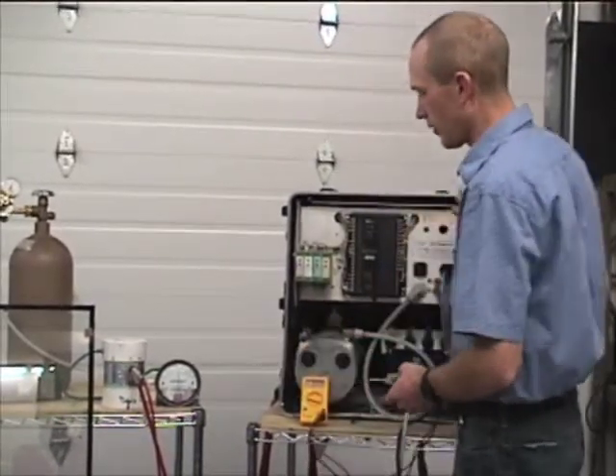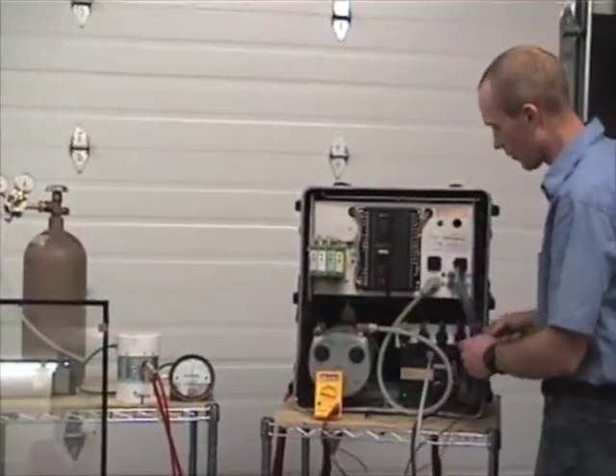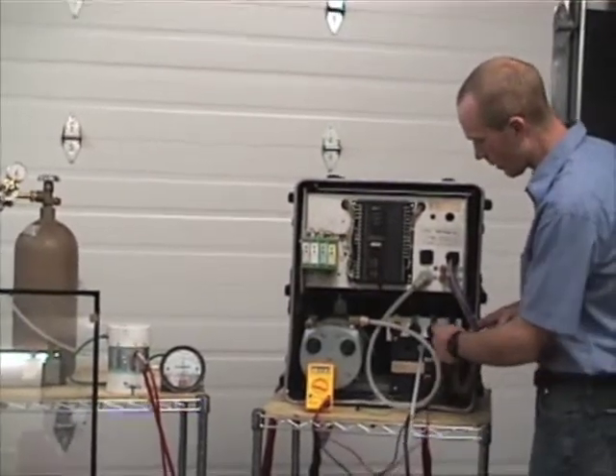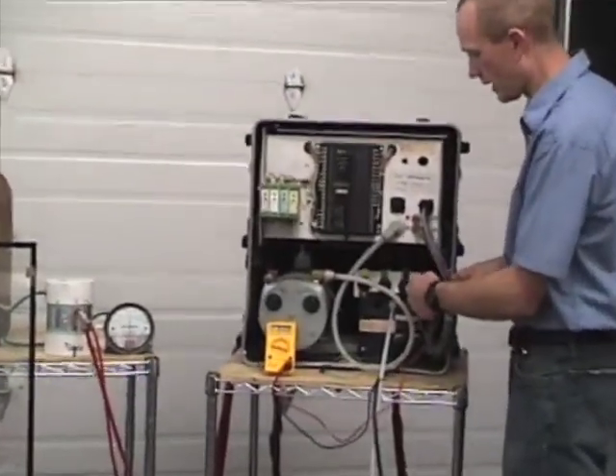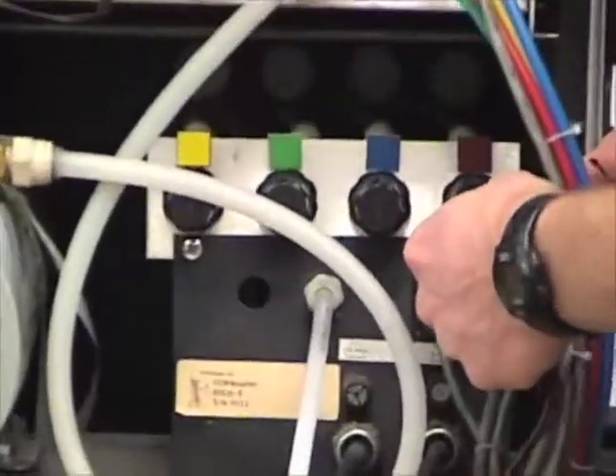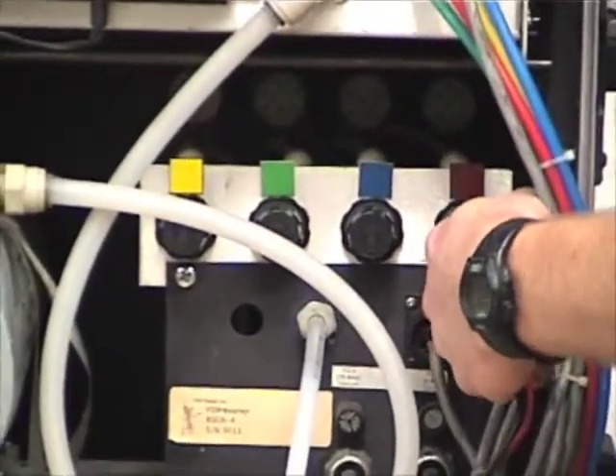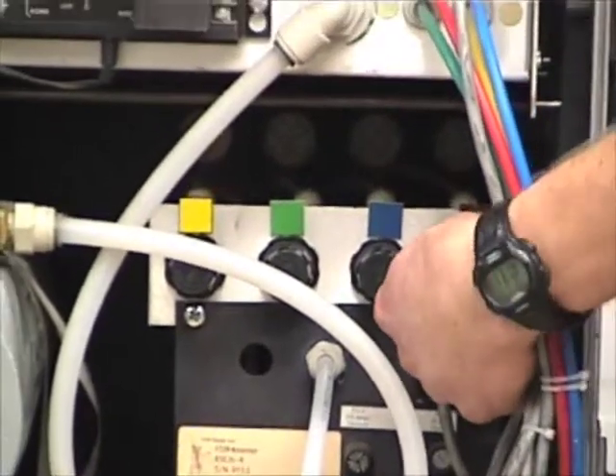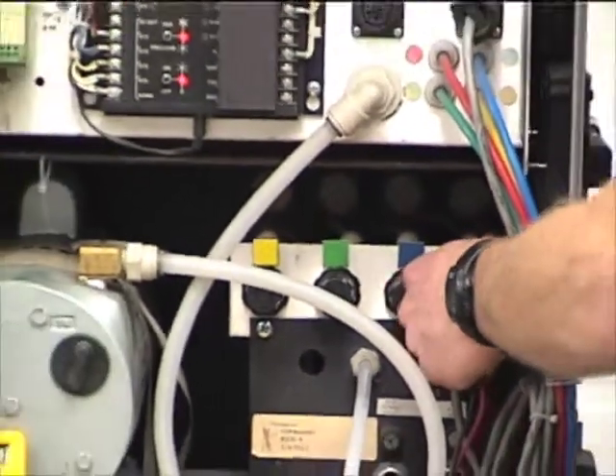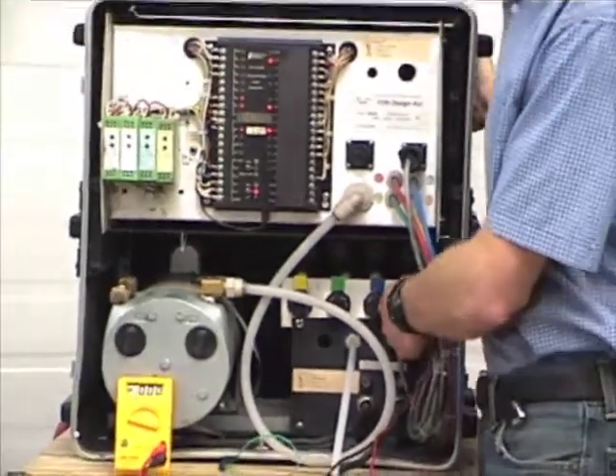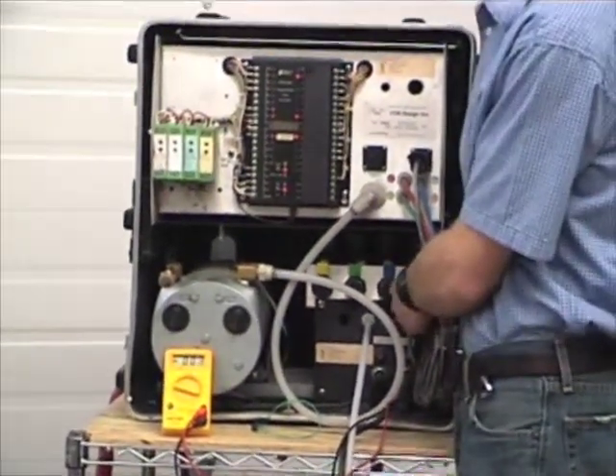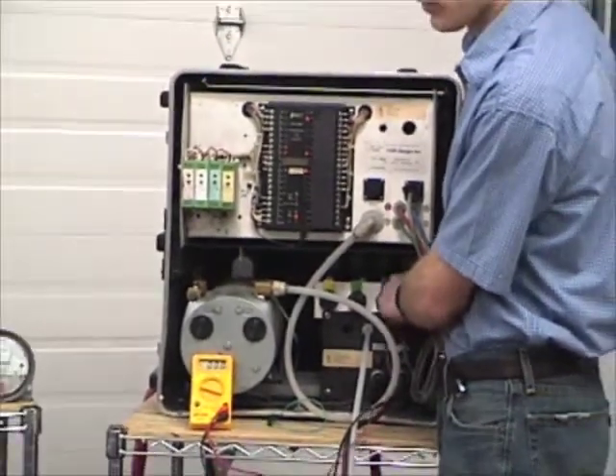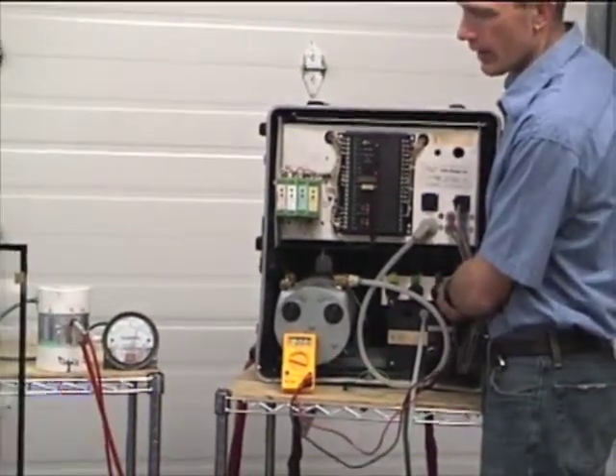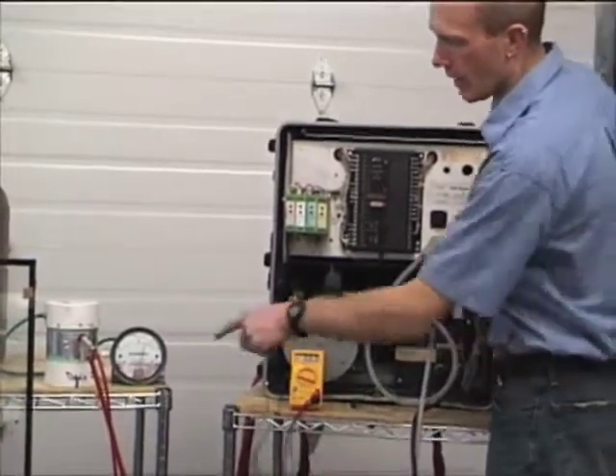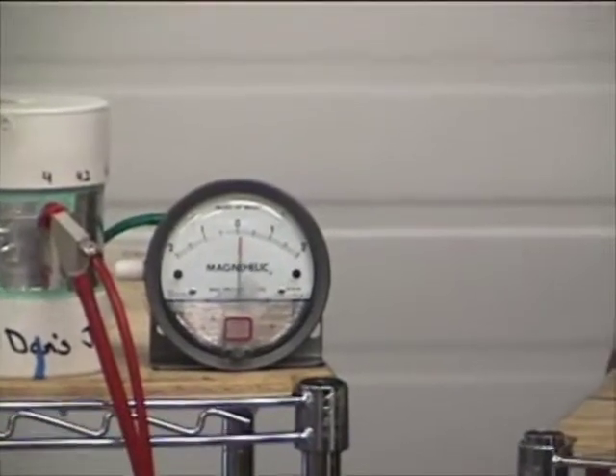I'll go ahead and start the machine, and again there's one regulator per line, so we'll have to do this per line again. I'll just do one for the demonstration, and this is my red regulator here. I'll start it. You want to be somewhere on the positive side. It really depends on the manufacturer. Some will go higher, some will go lower. The nominal setting is a 1/2 inch, so I'll just set it at a 1/2 inch positive on the magnehelic, and then I'll stop it.